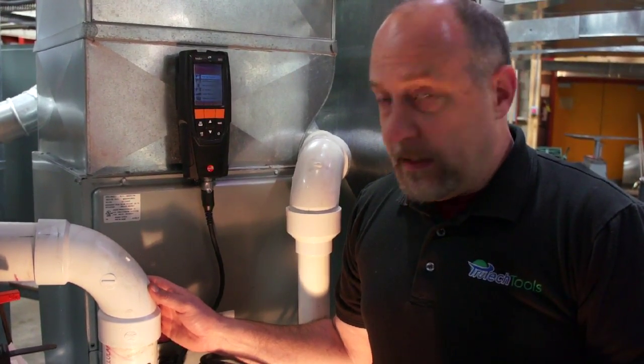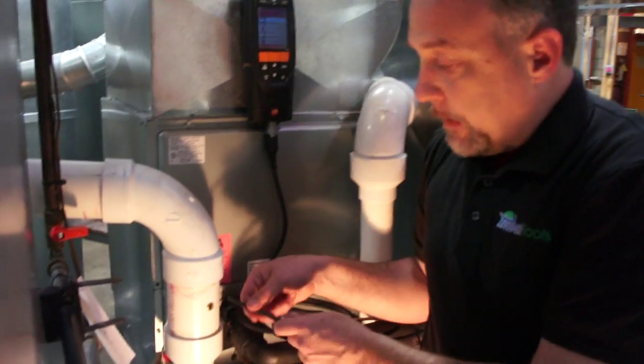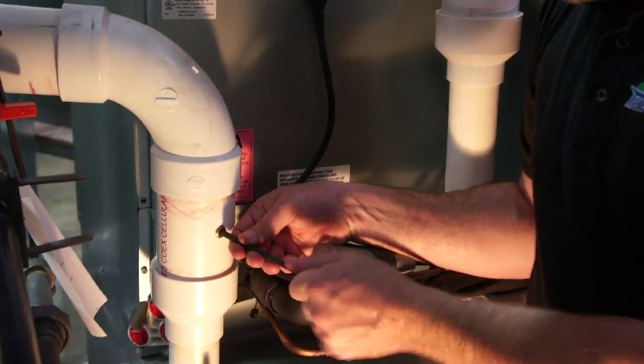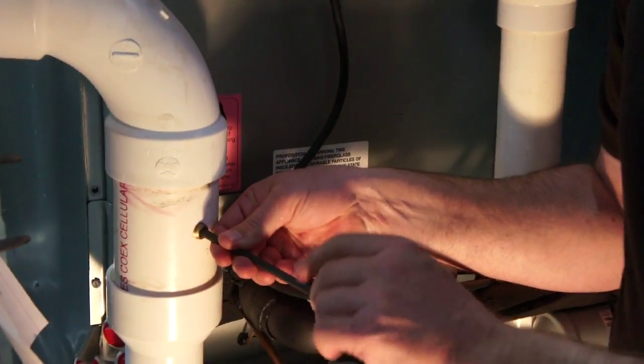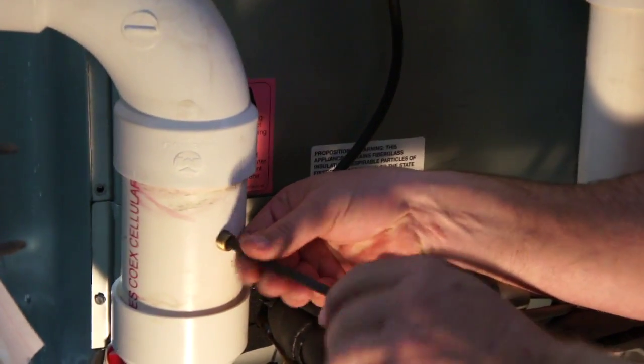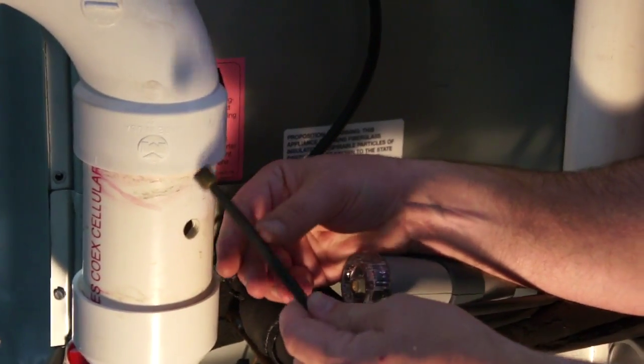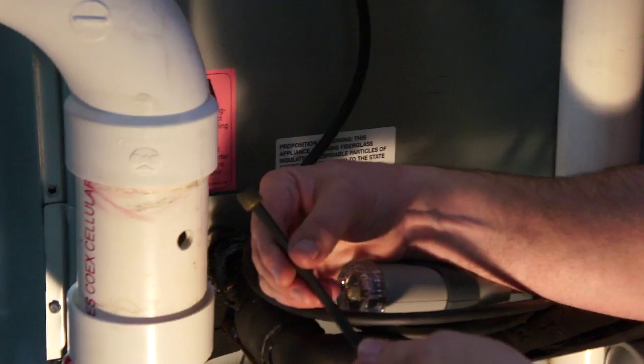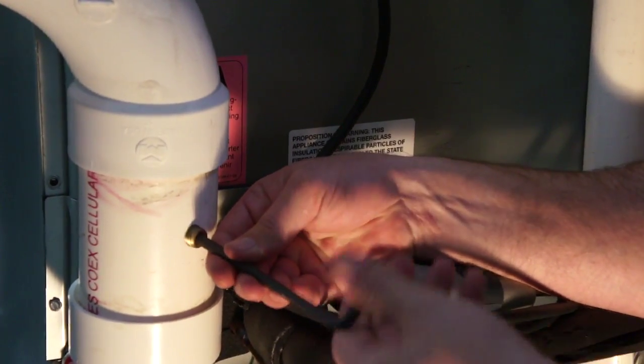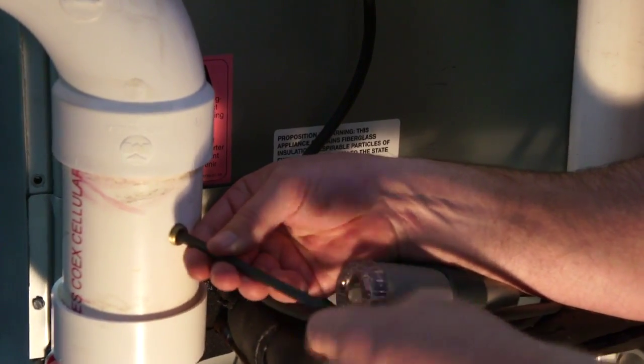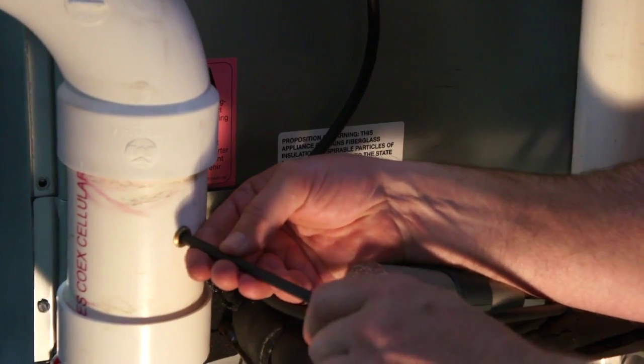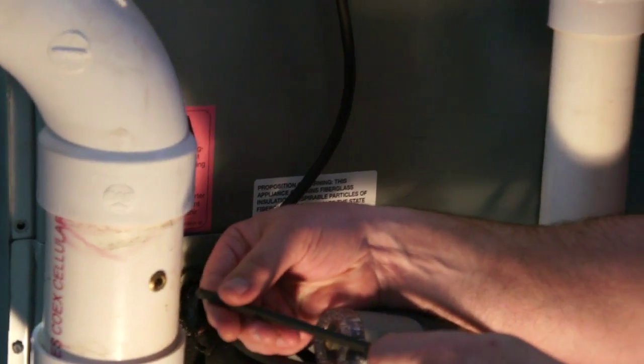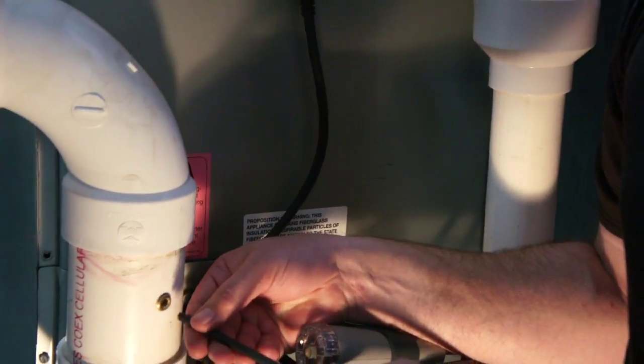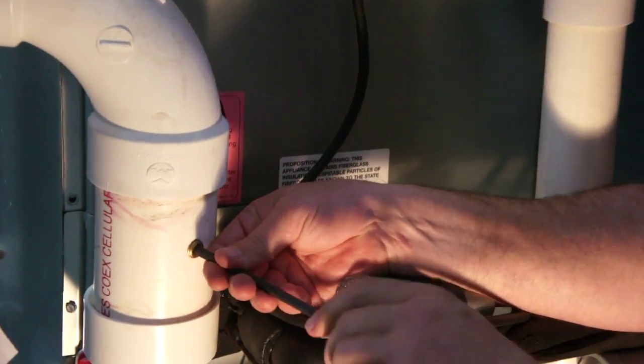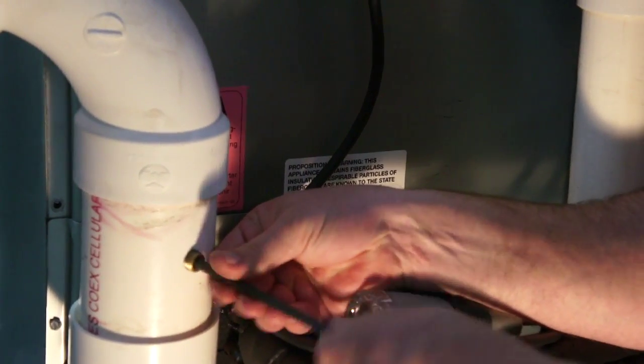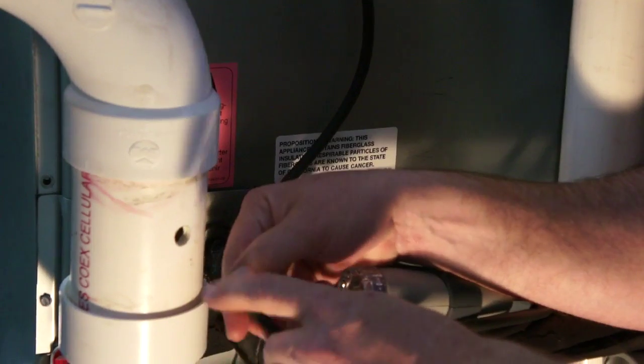I found the best way to seal the pipe up is right here with a brass pipe plug. So what I did here is I drilled a hole for this with a drill bit, and then all I did was use the pipe plug threads to actually tap the hole. It's soft pipe, it'll go right in there and tap, and because it's tapered, it provides a real nice positive seal. You can see that tightens up, and now I don't have to worry about that falling out again. I can easily take it in and out every year and have a nice port for combustion testing that I know is sealed, it's not going to leak into the home.